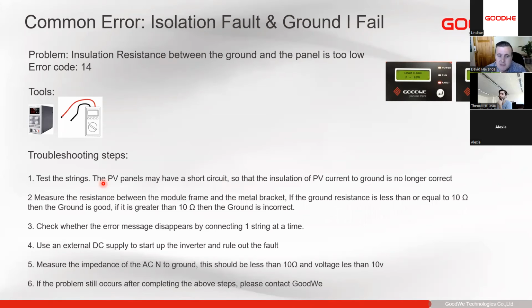We need to measure the resistance between the module frame and the metal bracket. So if the ground resistance is less than or equal to 10 ohms, then the ground is good. If it's greater than 10 ohms, then the grounding is incorrect. We need to check whether the error message is displayed.